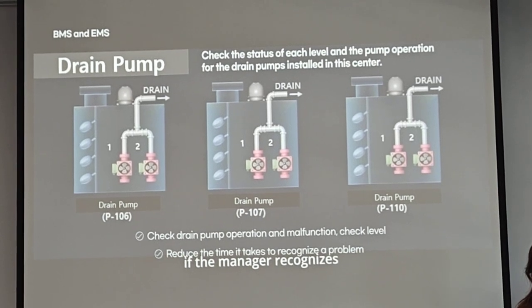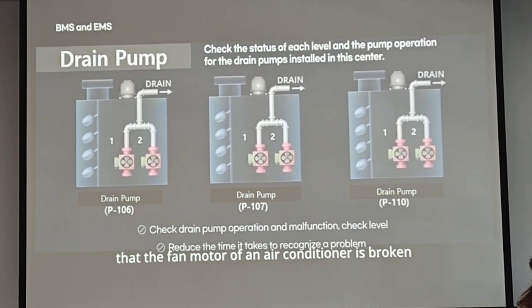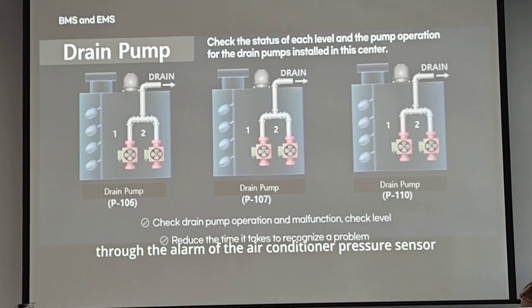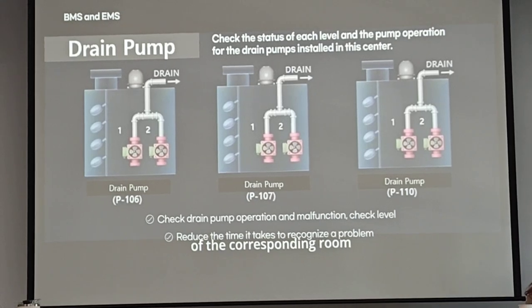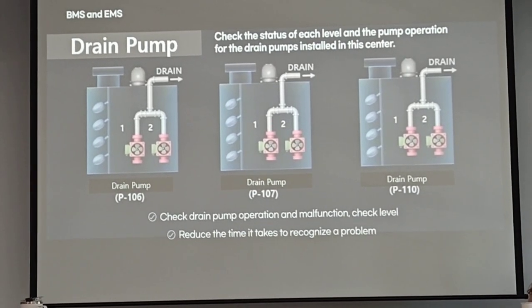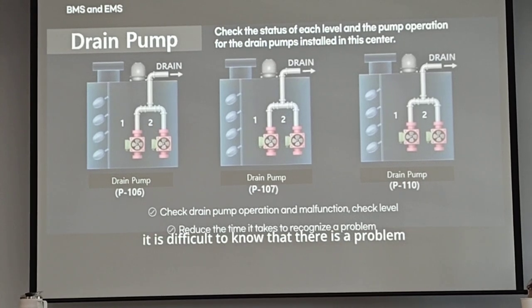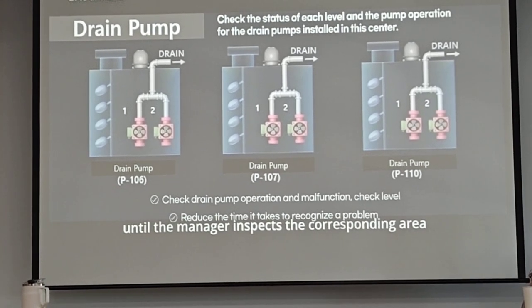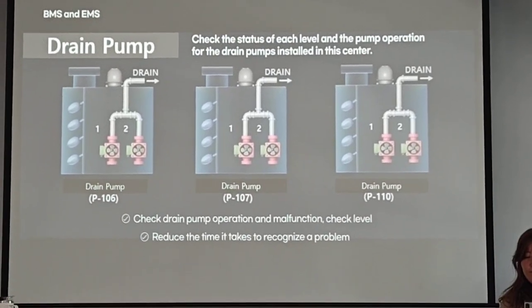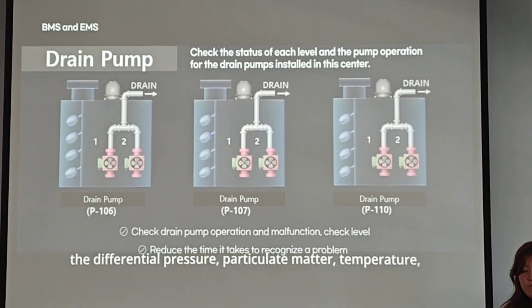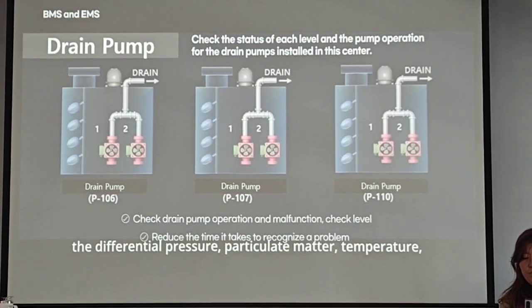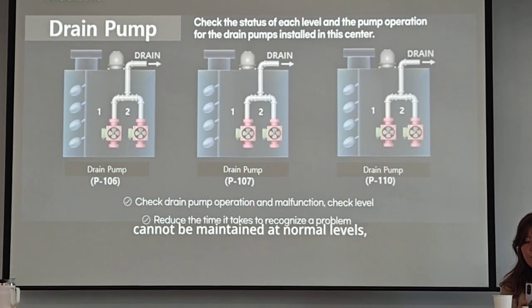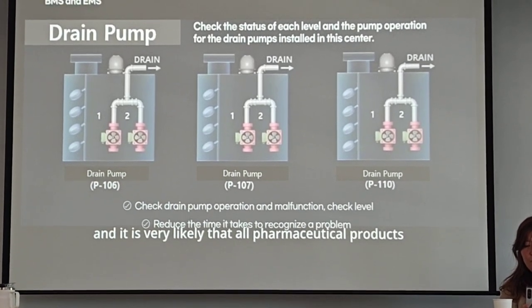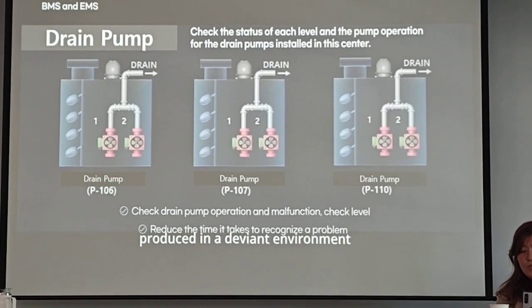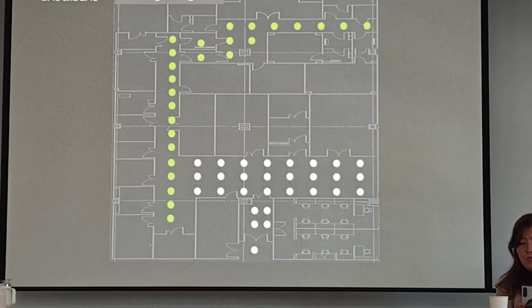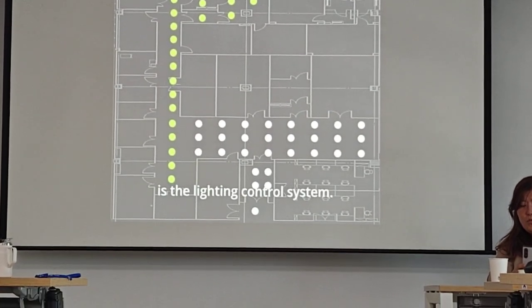For example, if the manager recognizes that the fan motor of an air conditioner is broken through the alarm of the air conditioner pressure sensor or the differential pressure sensor of the corresponding room, he or she can take immediate action. However, if the BMS is not installed, it is difficult to know that there is a problem until the manager inspects the corresponding area or air conditioner. If the unrecognized time continues, the differential pressure, particulate matter, temperature, and humidity environments of the corresponding area cannot be maintained at normal levels, and it is very likely that all pharmaceutical products produced in a deviant environment will have to be disposed of. The equipment you are currently viewing is the lighting control system.